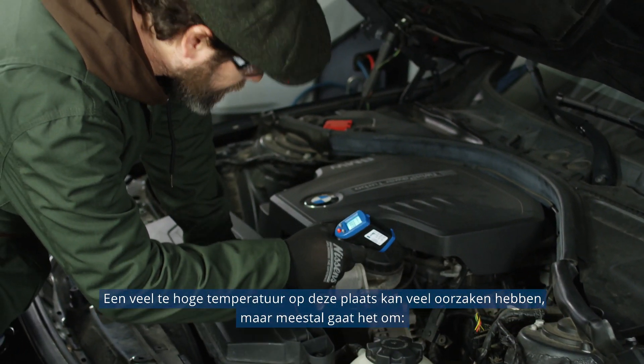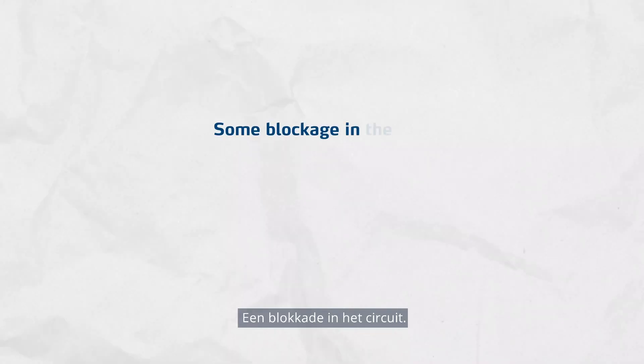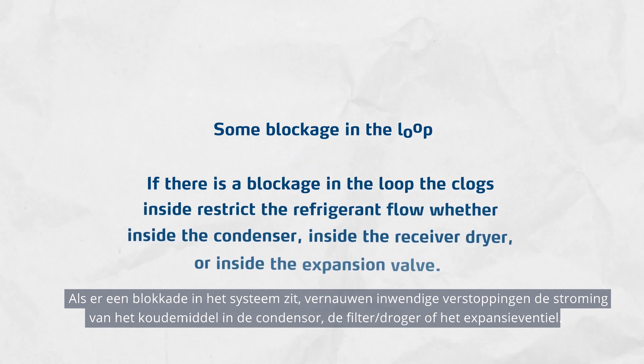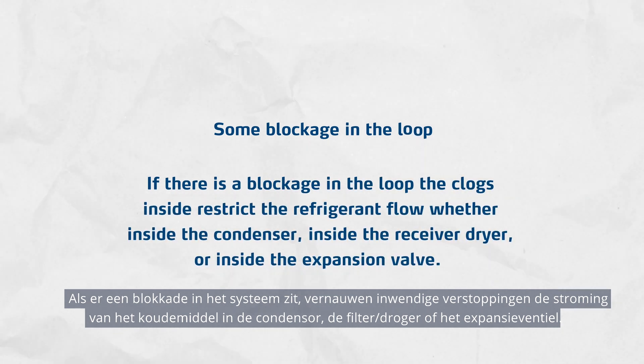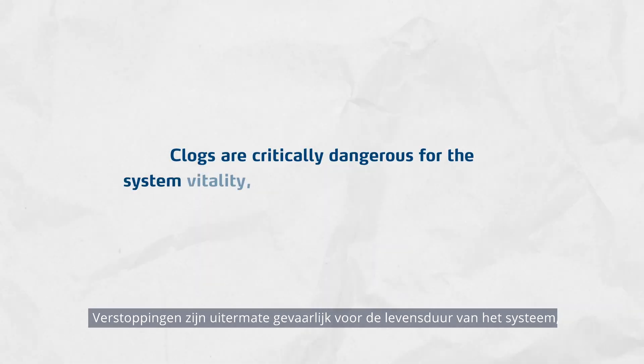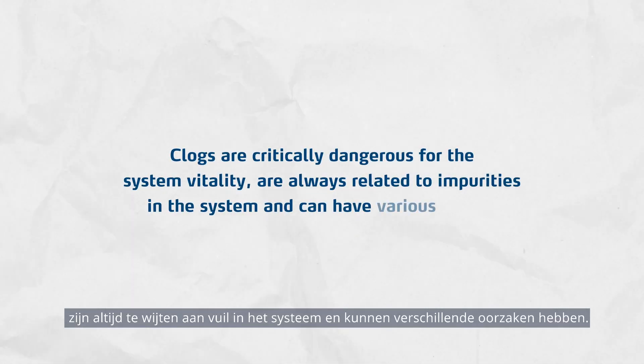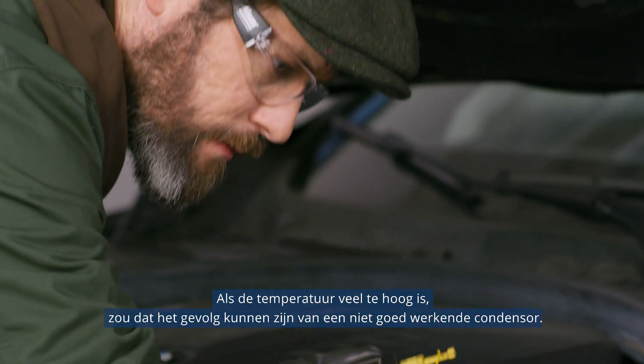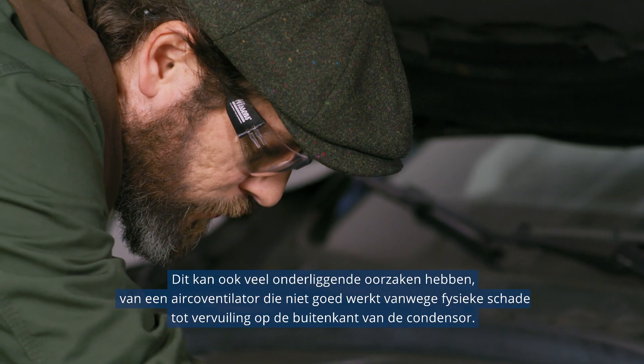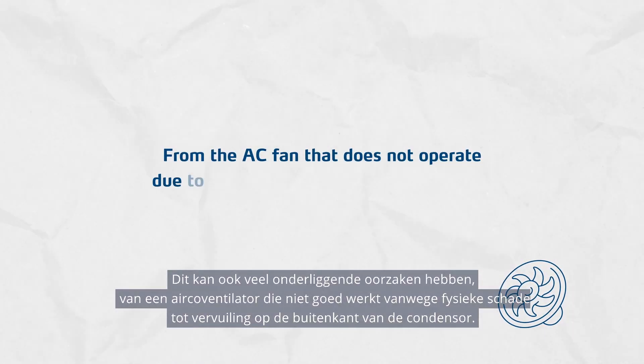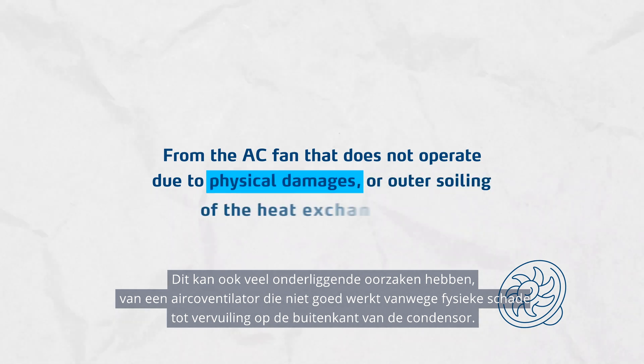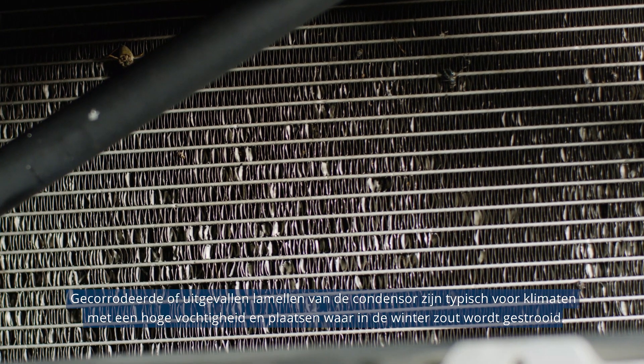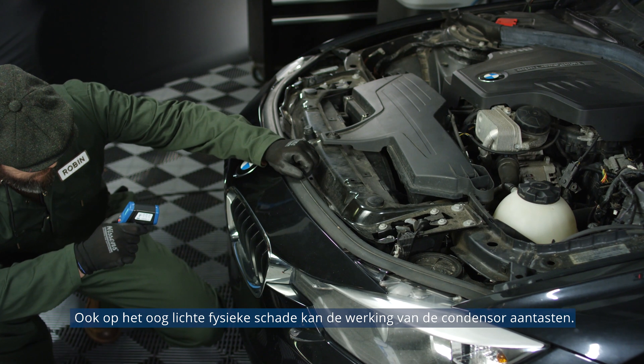A temperature that is way too high at this spot can mean many things, but here are the most common. Some blockage in the loop — if there is a blockage, the clogs inside restrict the refrigerant flow whether inside the condenser, inside the receiver dryer, or inside the expansion valve. Clogs are critically dangerous for the system's vitality, are always related to impurities in the system, and can have various origins. If the temperature is way too high, it could be due to improper operation of the condenser, which can have many potential root causes, from the AC fan not operating due to physical damages or outer soiling of the heat exchanger surface. Corroded and missing fins are typical for climates with a lot of moisture and where salt is spread during the winter. Seemingly light physical damages can reduce operation of the condenser.